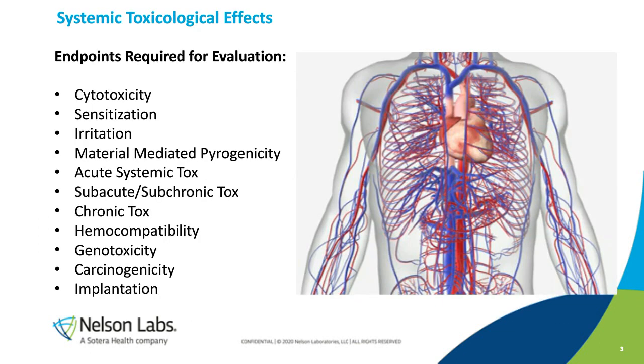If you have a medical device that is going to be submitted for regulatory clearance, then to try to safeguard the health of people using those devices, it needs to be demonstrated that the device is biocompatible before a regulatory body is going to approve it, right? And this is just to prevent these devices from harming somebody rather than helping them.